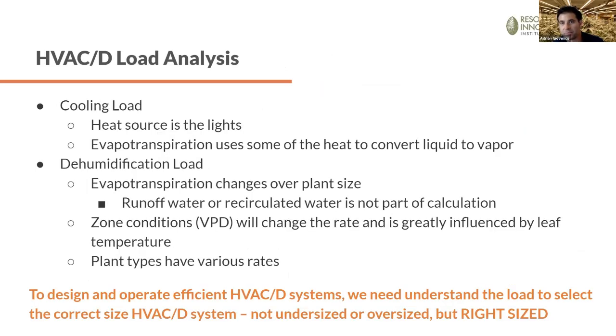We can go to the next slide and talk a little bit about the load in general. This could be a 60-minute seminar in and of itself, going deep into the load design and analysis. We put out webinars on this type of topic often. We effectively have two types of load in the space. We have the dehumidification load that we just talked about, and we have a cooling heat load from the lights. We need to balance and be able to manage and serve that with a system, whether it be a non-integrated system that Brian just talked about, or an integrated system where you're doing dehumidification and cooling and heating together with the same system. Either way, you need to be able to effectively control both the sensible heat load in the space as well as the moisture removal requirement.